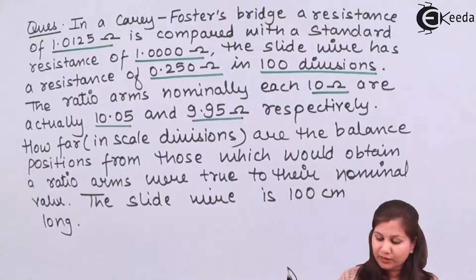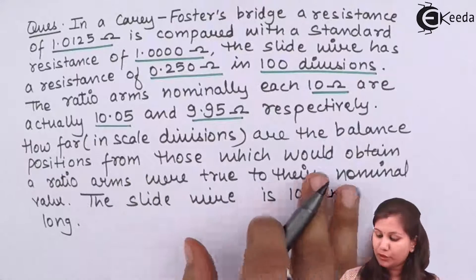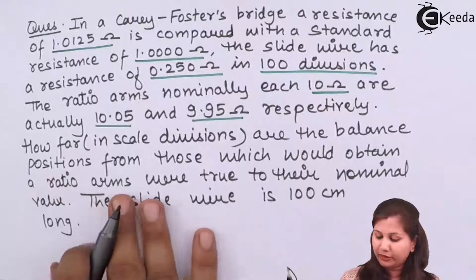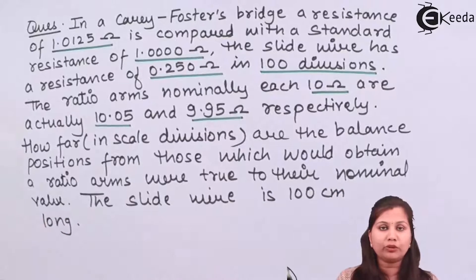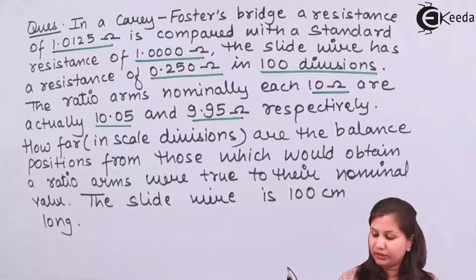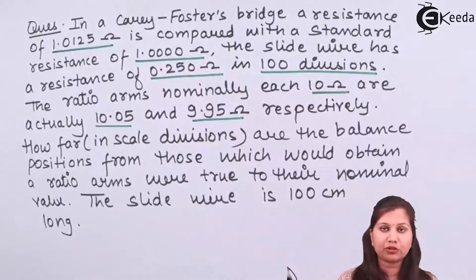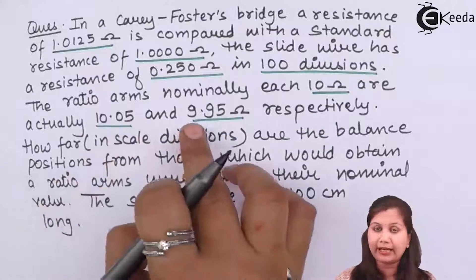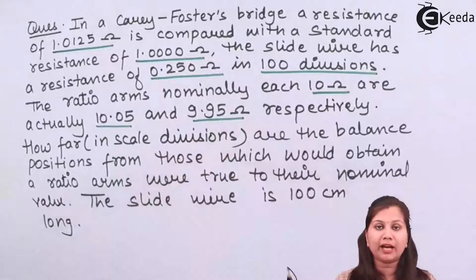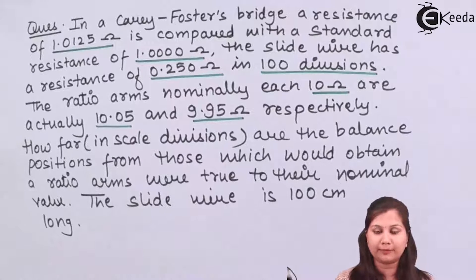We have to calculate how far the balance positions are from those which would be obtained when the ratio arms were true to their nominal value. So we take two measurements: one with the nominal value of the ratio arms as 10 ohm, and another when the values are 10.05 and 9.95, and find the difference between the two measurements.